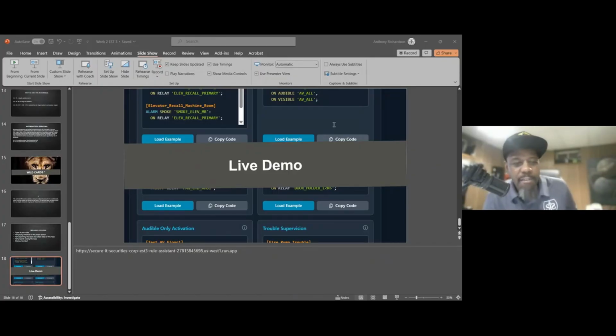You have AC, so the system doesn't automatically send out this trouble signal. When you're setting up the modcom, you will have to configure these messages so that you can get your brownout, your ground faults, and all these other different trouble messages. And if you're installing or writing rules for a voice system, you want to make sure you use the qualifier message on to turn on the evacs, not just on.